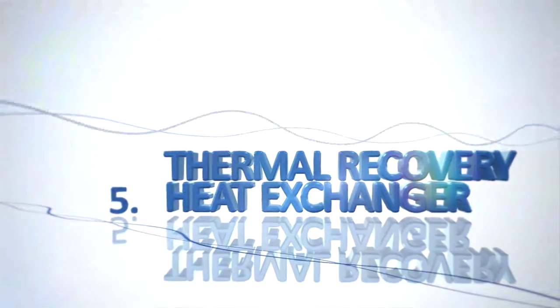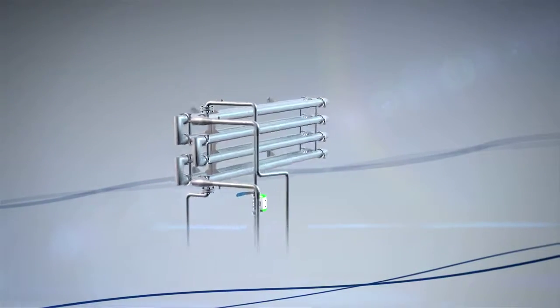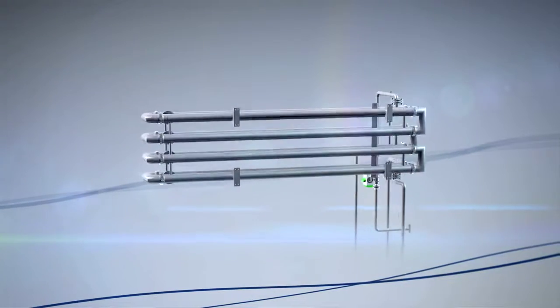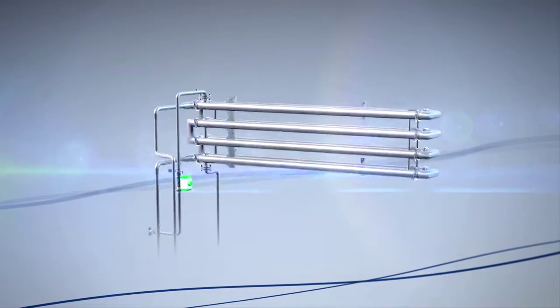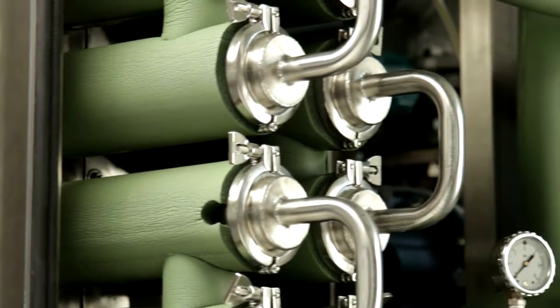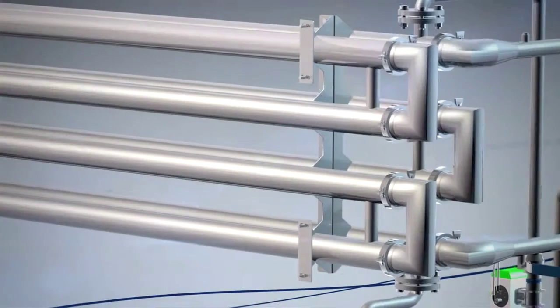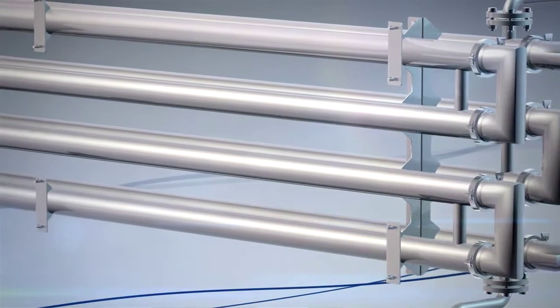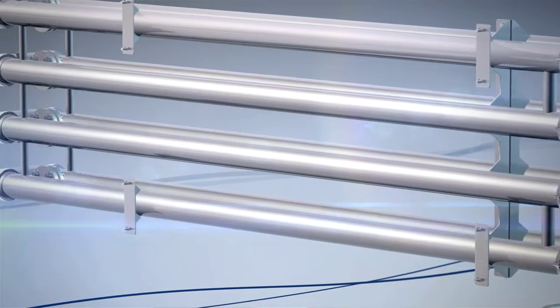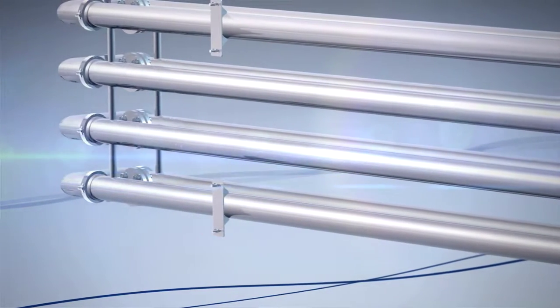We are now nearing the end of our brief summary, and we would like to focus on the optional system for heat recovery, the recovery heat exchanger, from concentrate to waste. First of all, it is easy to inspect and maintenance time is reduced. The heat exchange surface has been tripled, as well as the possibility to reduce energy consumption, even with the highest concentrated wastewater at the inlet.